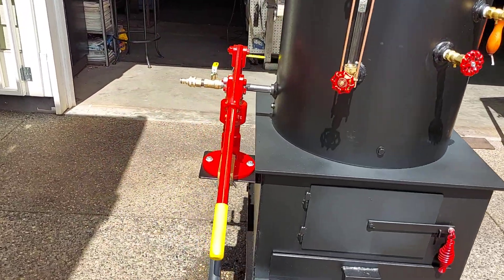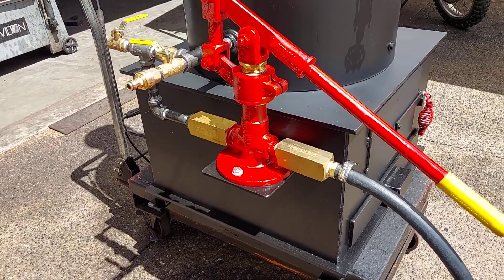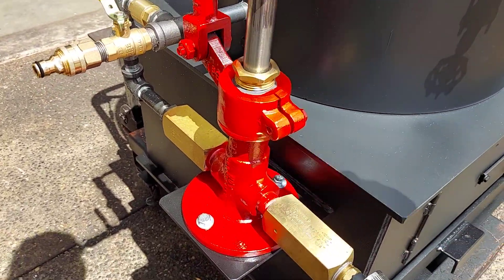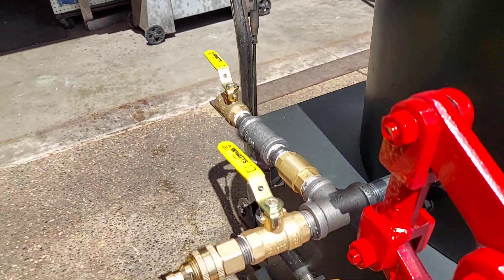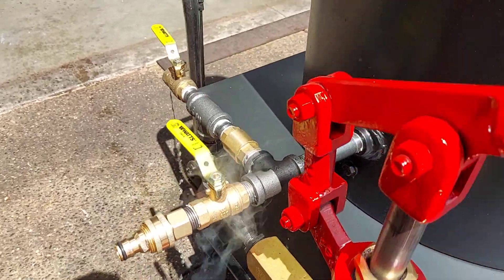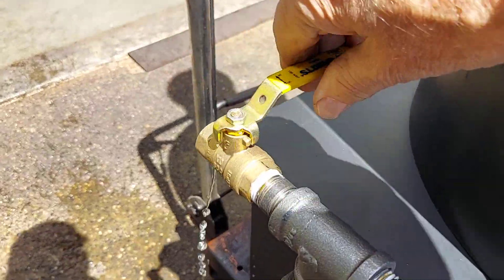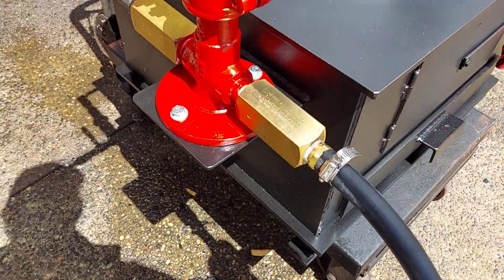It has a really nice hand pump, one inch ram on it. I'll pump it a few times here. This is your airlock valve. If you're just starting out the pump, just putting it in water, it'll need to prime the pump. Close that off, get the air out of it, and then everything now goes right into the boiler.